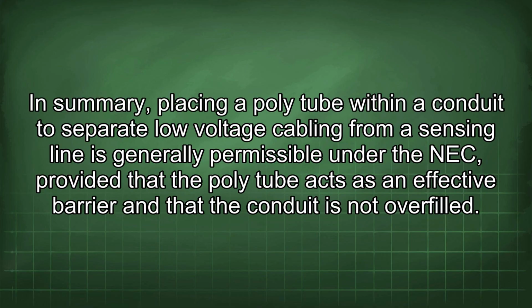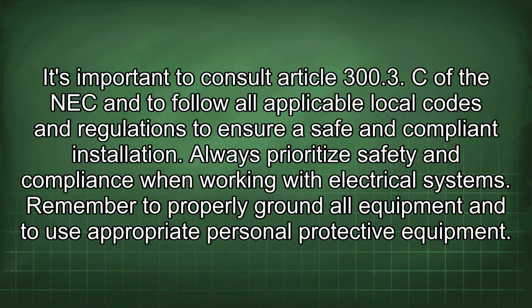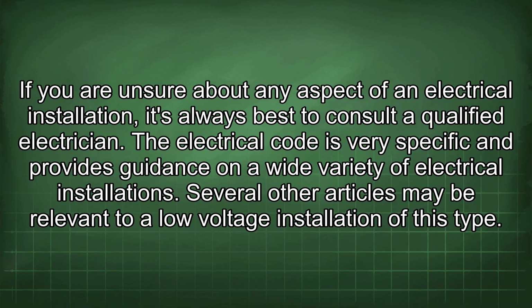In summary, placing a polytube within a conduit to separate low-voltage cabling from a sensing line is generally permissible under the NEC, provided that the polytube acts as an effective barrier and that the conduit is not overfilled. It's important to consult Article 300.3(C) of the NEC and to follow all applicable local codes and regulations to ensure a safe and compliant installation. Always prioritize safety and compliance when working with electrical systems. Remember to properly ground all equipment and to use appropriate personal protective equipment. If you are unsure about any aspect of an electrical installation, it's always best to consult a qualified electrician. The electrical code is very specific and provides guidance on a wide variety of electrical installations.